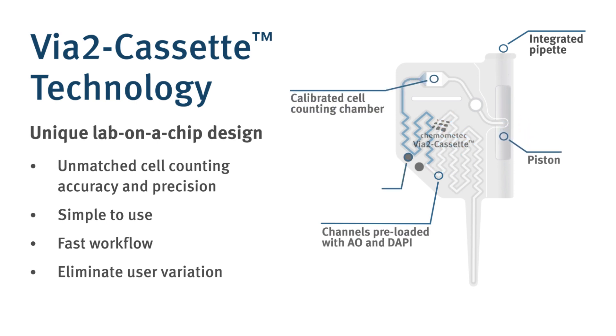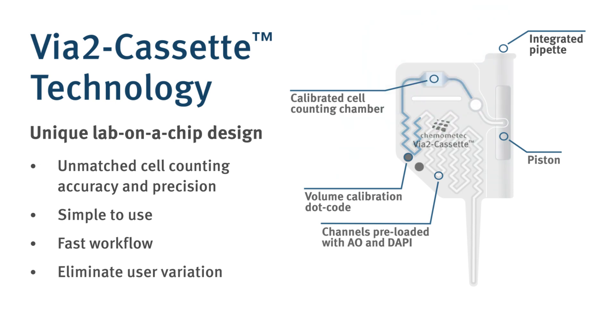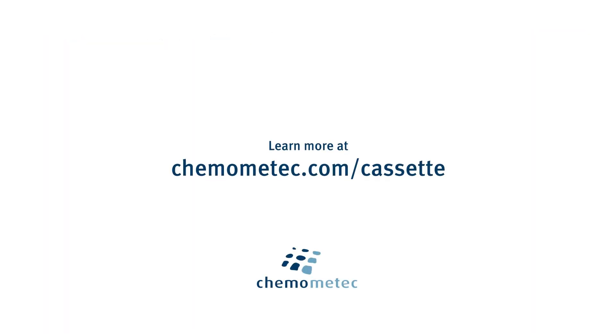The counting chamber of each VIA2 cassette is carefully volume calibrated, ensuring maximum precision. Fluorescent images of the AO and DAPI stained cells are taken and analyzed by the instrument. You've done a cell count in less than 30 seconds.